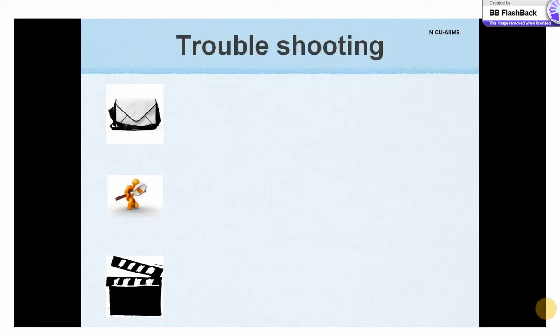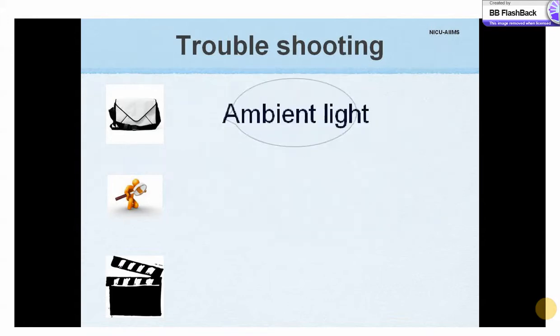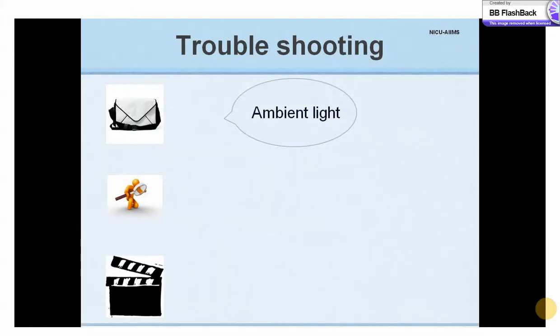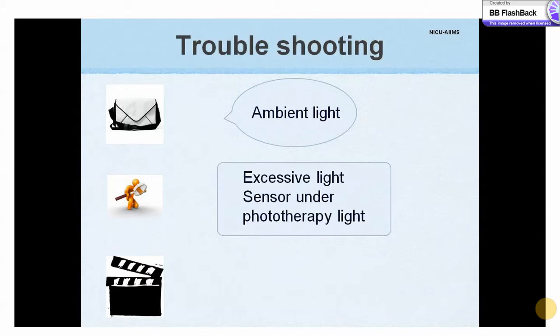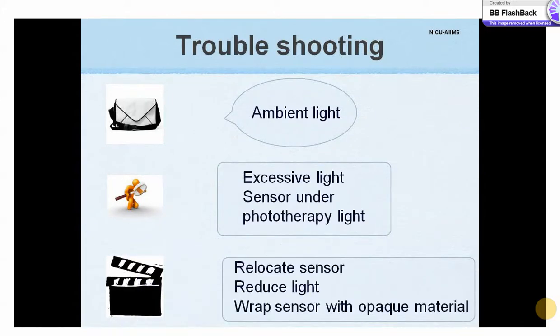Problems are anticipated while working with any equipment, and we should be able to fix them by analyzing the cause and finding a solution. If there is a message quoting ambient light, it means there is excess light shining on the sensor — relocate the sensor to a more shielded site or reduce the amount of light. If the baby is under phototherapy, the sensor must be wrapped with an opaque cloth or carbon paper.